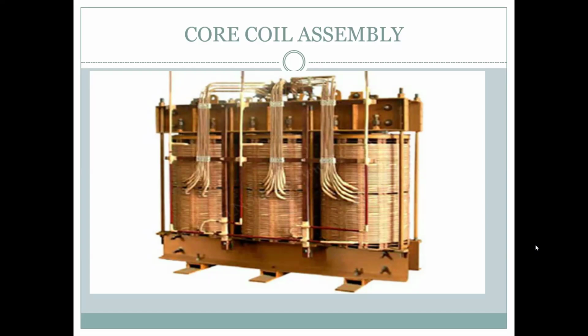Now these insulations are hygroscopic. They absorb moisture from outside. So they have to be dried, because if moisture is there, it is like accumulated water in your lungs. It has to be dried out, extracted out. So it goes to the oven. Every KV class has a particular cycle of heating under pressure, and this cycle is to be maintained for 36 hours, 48 hours depending on that. So it goes to the oven and the entire moisture is taken out.